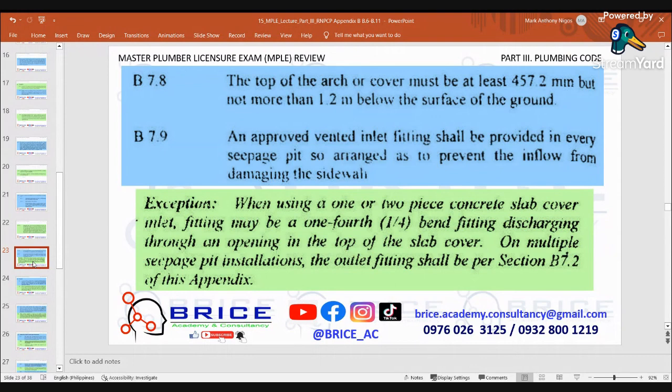The top of the arch or cover must be at least 457.2mm but not more than 1.2m below the surface of the ground. Inlet fitting shall be provided in every seepage pit, so arranged as to prevent the inflow from damaging the side wall. Exceptions: when using a 1 or 2 piece concrete slab cover, the inlet fitting may be a 1/4 bend fitting discharging through an opening in the top of the slab cover.